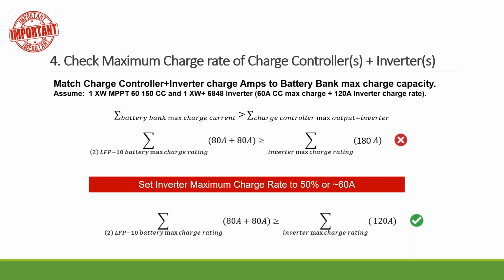So in this case, the two LFP-10 together allow you to charge the battery at 160 amps. Now if you allow the inverter and solar to run at full capacity, you need 180 amps. That's a whole 180 amps together. Now 160 amps is smaller than 180 amps. What's going to happen? You're going to overcharge the battery, right? You don't want to see that. Then what you can do is, the system is designed to be flexible. You can let the charge controller run at full capacity if there's plenty of sun.